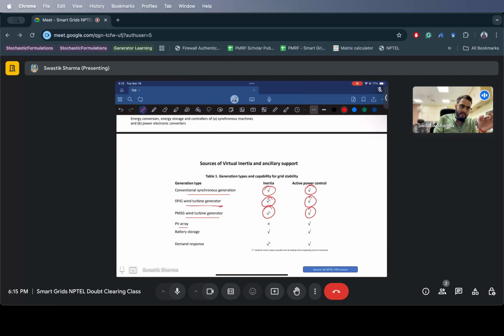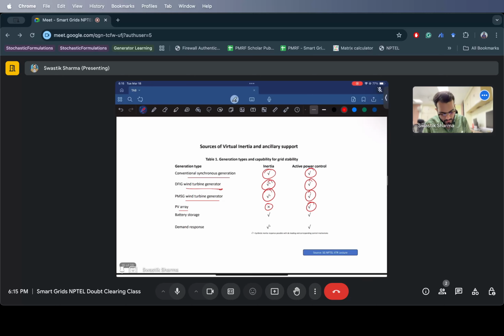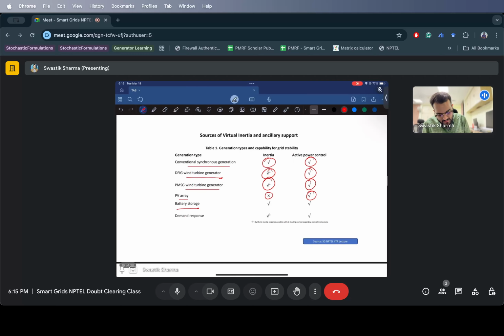If you don't have a battery, you cannot have inertia, but you can control active power out of it because you have active power set points. By controlling the active power set points, you can control the active power output from the PV array. Your battery storage acts like a synthetic inertia system. It has synthetic inertia, so there should be an asterisk over there as well.